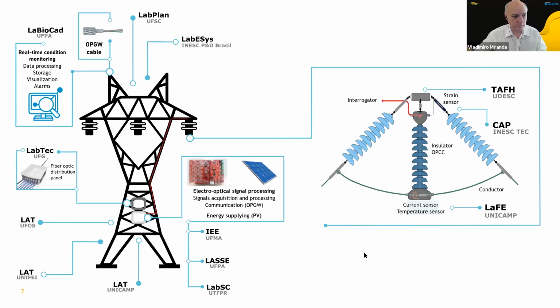Right now I'm going to say a little about the high voltage unit, which has been tested through several tests at the Federal University of Campina Grande, Unifei (Federal University of Itajubá), and Unicamp (Universidade de Campinas). The insulator itself is the path through which the fiber optics goes, and the sensors are in the lower part of the insulator. We call it the bell, due to its shape—it reminds us of a bell. Of the three sensors, one of them is not inside the bell, it's right here—it's a strain sensor. We're going to take a detailed look at each of these subsystems.